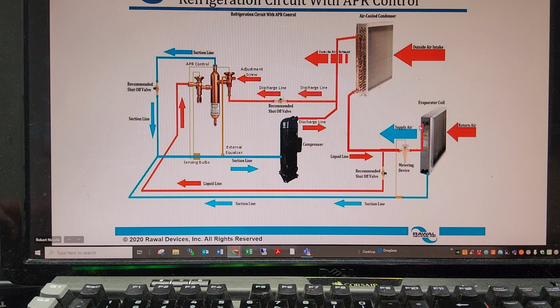And it's just a race between whether the set point gets met or the freeze protection goes off. And exactly. It's insane that this guy did not spec digital, what do you call it? Digital scroll.